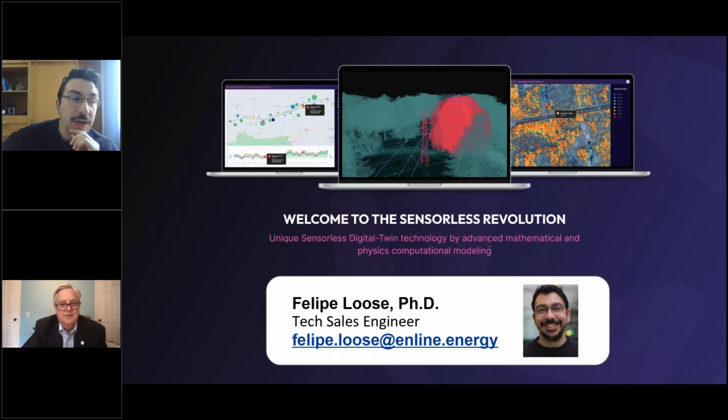Yeah, we are having a nice penetration in South America, especially with the network state estimator. We're still working with some customers on that, on the phase of deploying the module of the network state estimator. Also in Europe, we have other clients who are working with the thermal model and with this dynamic view of the grid, by changing the current control philosophy to temperature control, now by sensing it.